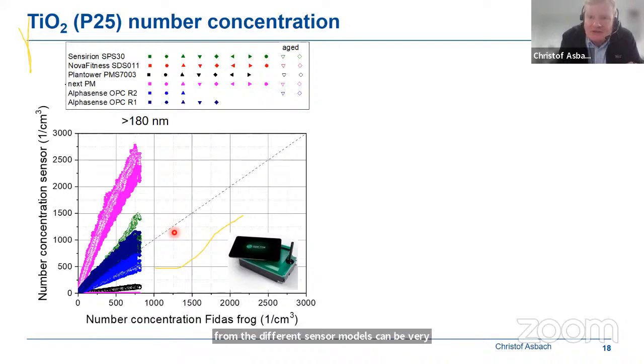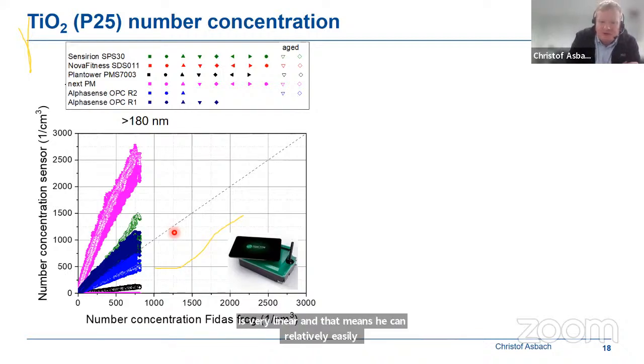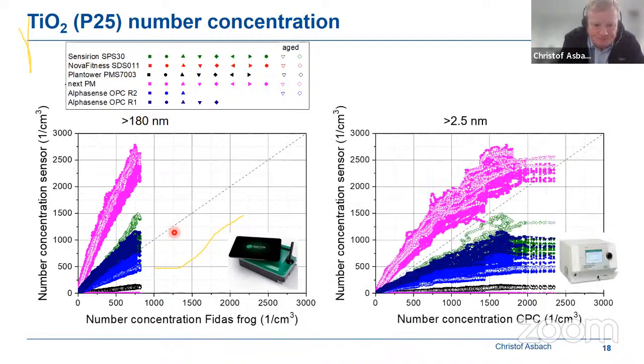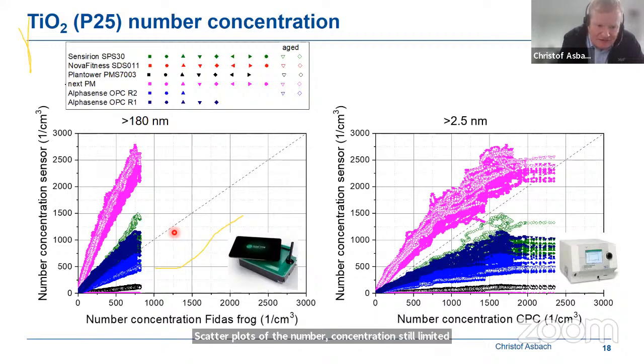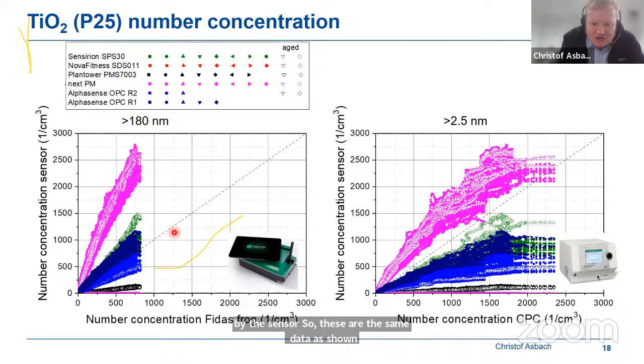But something else that can be seen is the response is very linear. And that means you can relatively easily recalibrate the sensors because it's just a linear response, as I will show in the next slide. But before that, I would also like to show you the scatter plots of the number concentrations delivered by the sensors. So these are the exact same data as shown in the left graph, but now against the number concentrations measured with a condensation particle counter.